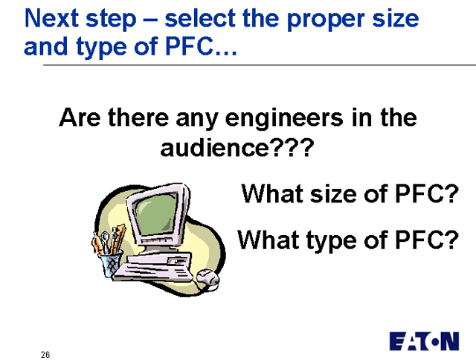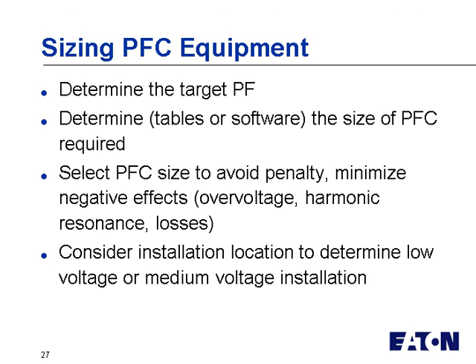Now, again, remember the steps I said were that you have to, first of all, figure out what the penalty is, and then you just select the equipment. Well, the next step is really to select the size and type of power factor correction, and that can be problematic as well because it can be somewhat confusing. But I will tell you that there are tools available to figure that out. You determine, first of all, the target power factor. So if the utility says you have to maintain a 0.95, then that's your target power factor. If they say that you're on kVA rates or your power factor should be unity, then that's your target power factor. Then you can typically easily determine with tables or software the size of power factor correction equipment required.